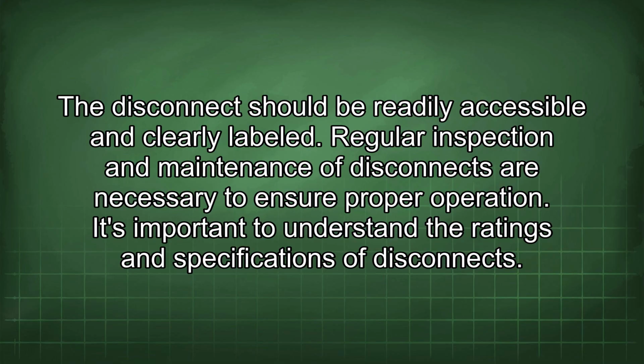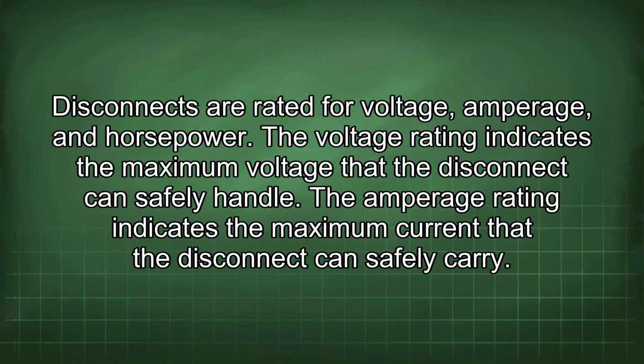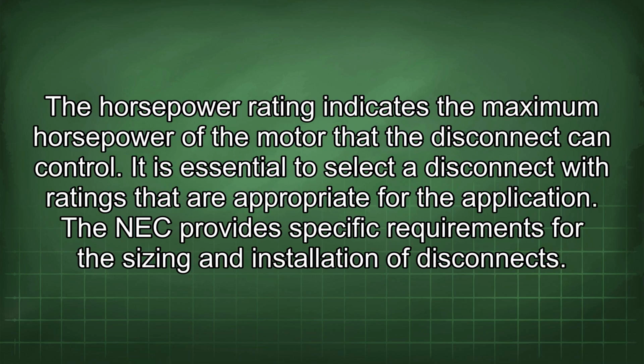It's important to understand the ratings and specifications of disconnects. Disconnects are rated for voltage, amperage, and horsepower. The voltage rating indicates the maximum voltage that the disconnect can safely handle. The amperage rating indicates the maximum current that the disconnect can safely carry. The horsepower rating indicates the maximum horsepower of the motor that the disconnect can control. It is essential to select a disconnect with ratings that are appropriate for the application.